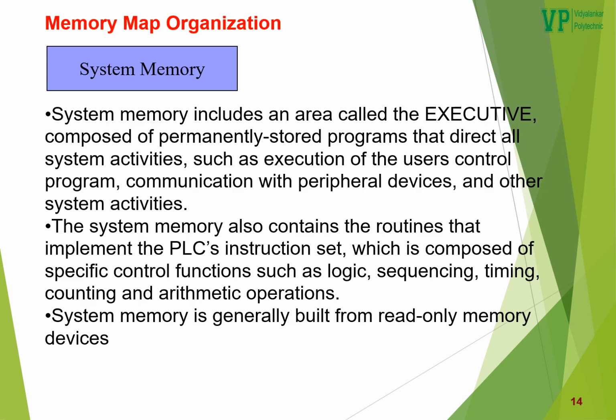System memory is generally built from read-only memory devices. Well, it means system memory is loaded with a firmware. This firmware has instructions to run a PLC. At the same time, it could also have diagnostic programs of PLC and other subroutines which are pre-written by the manufacturer. However, the user cannot make any change to any of the programs written in system memory, and hence system memory is generally built from read-only memory devices.